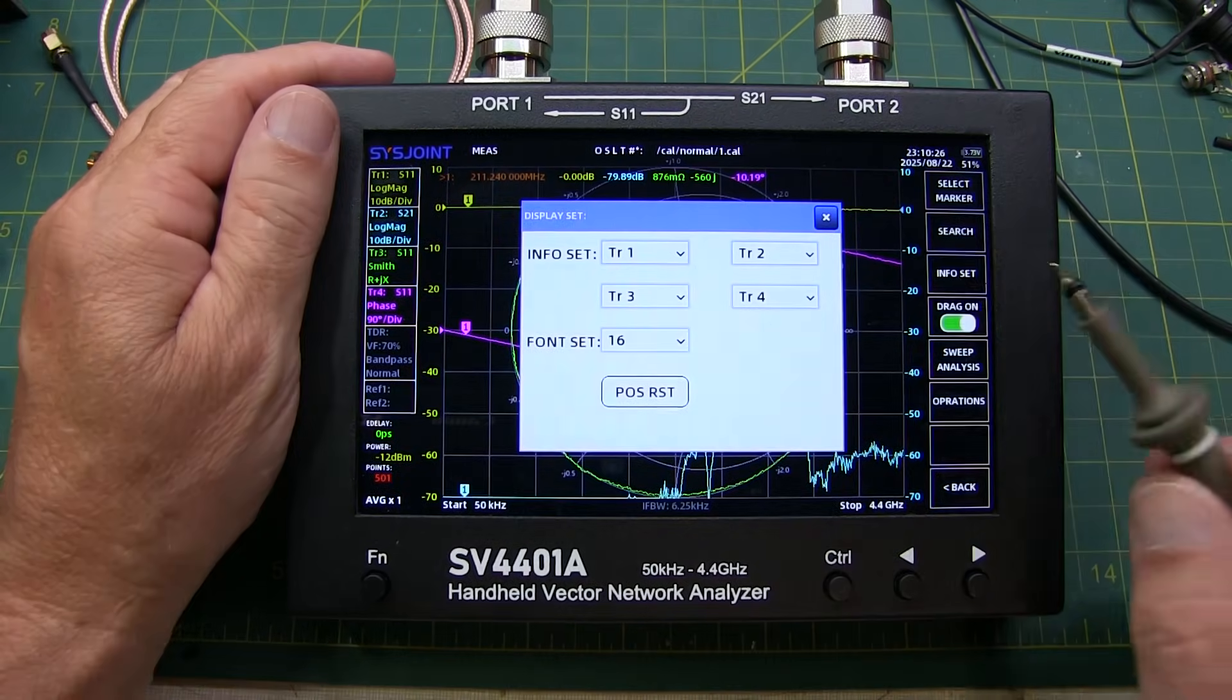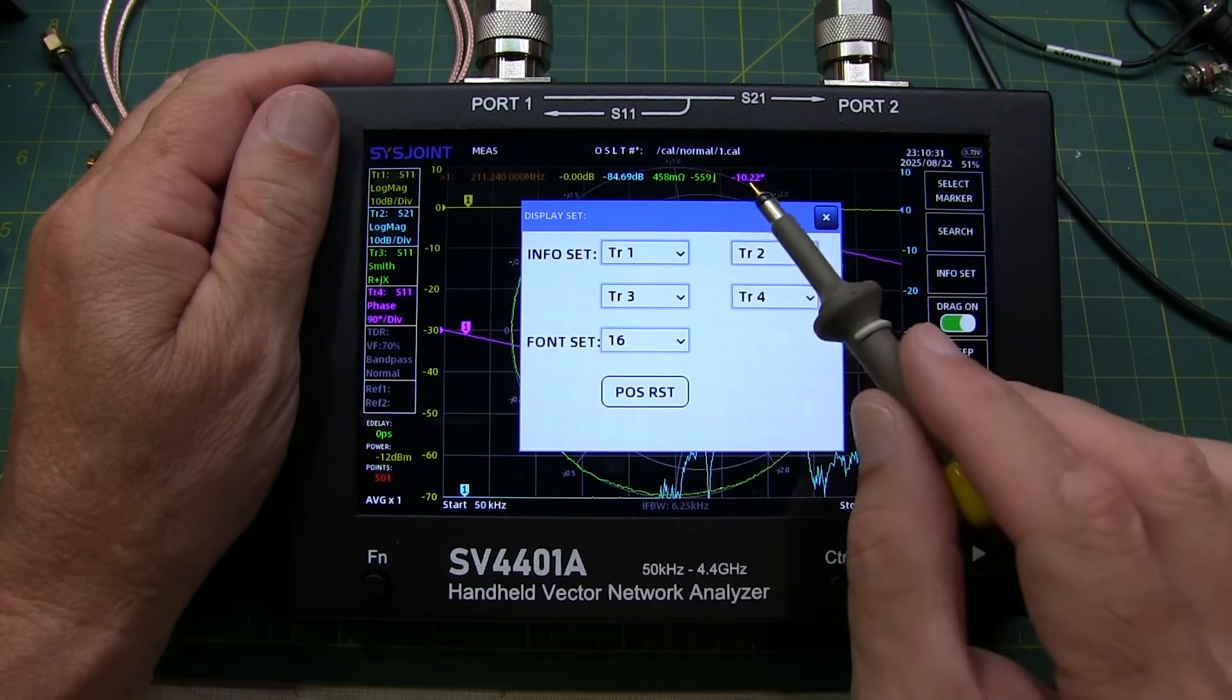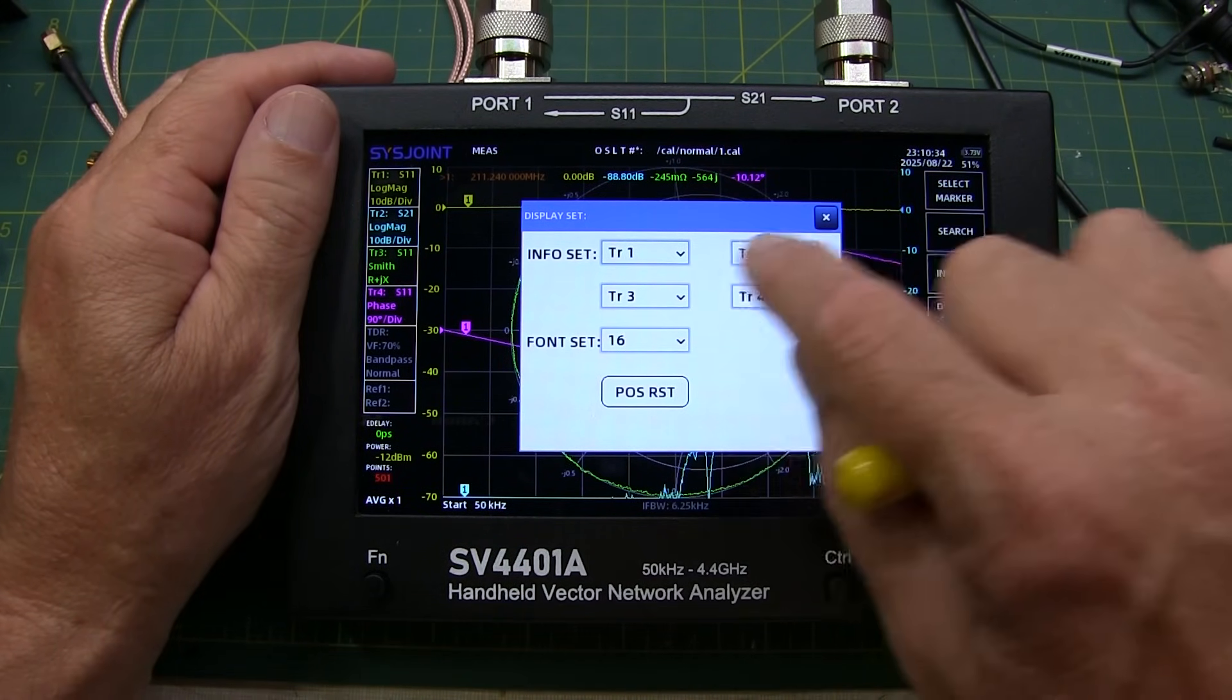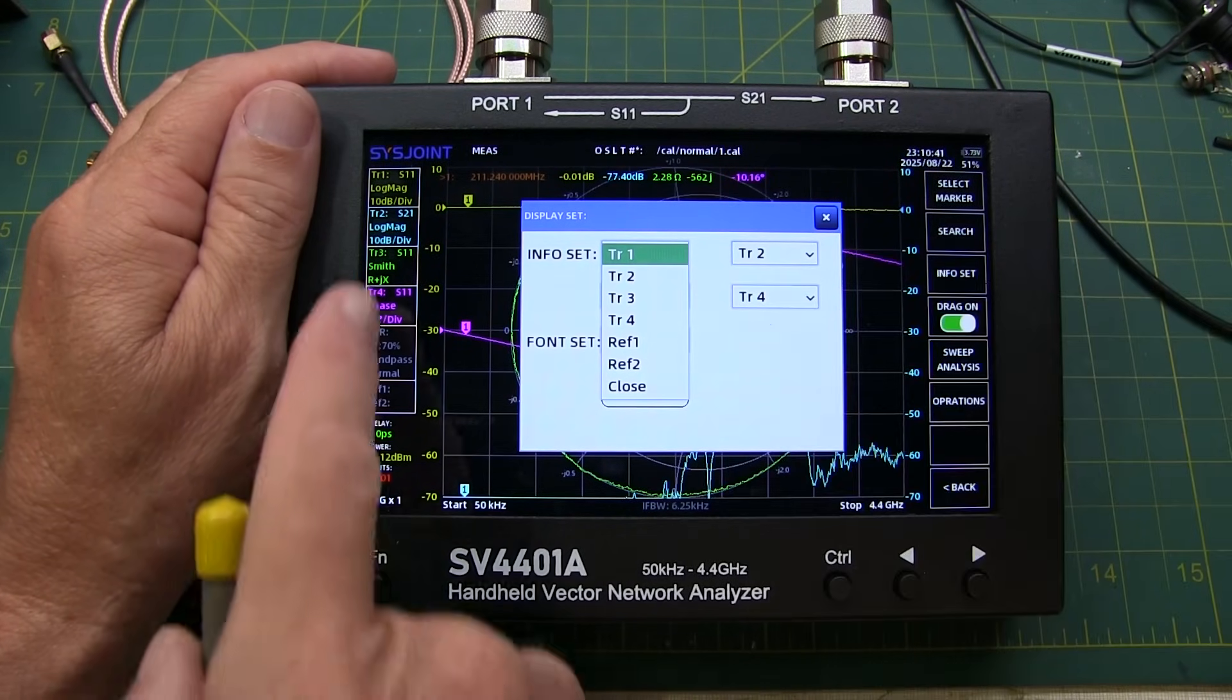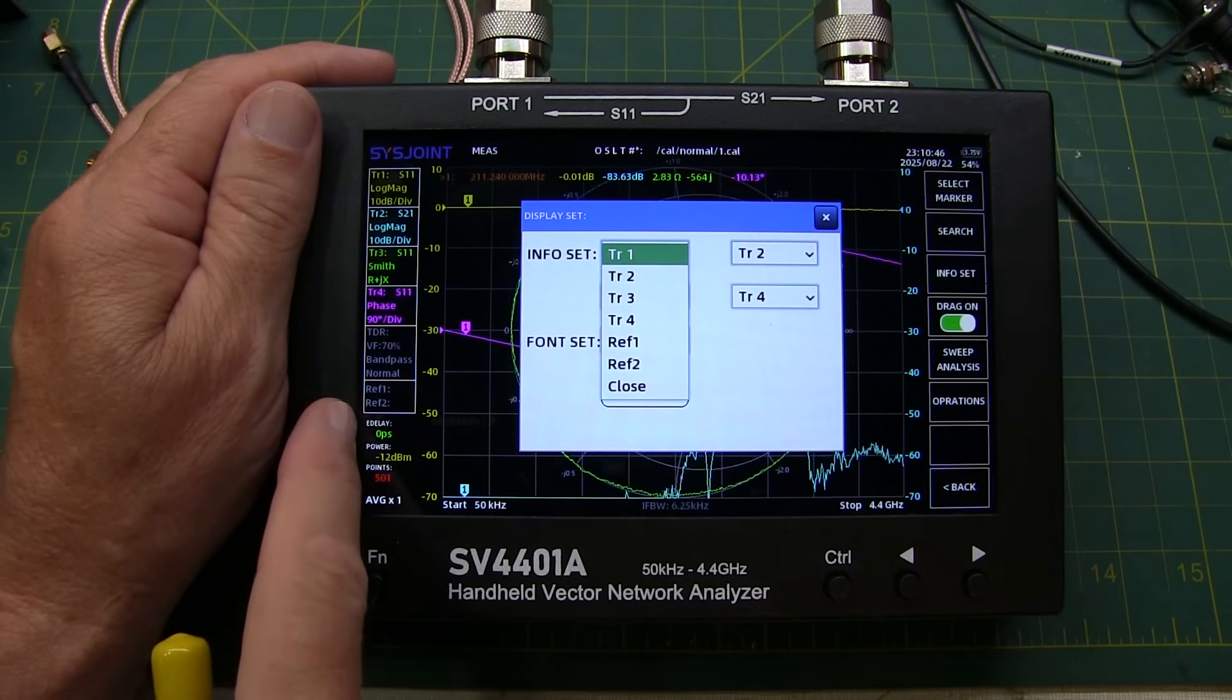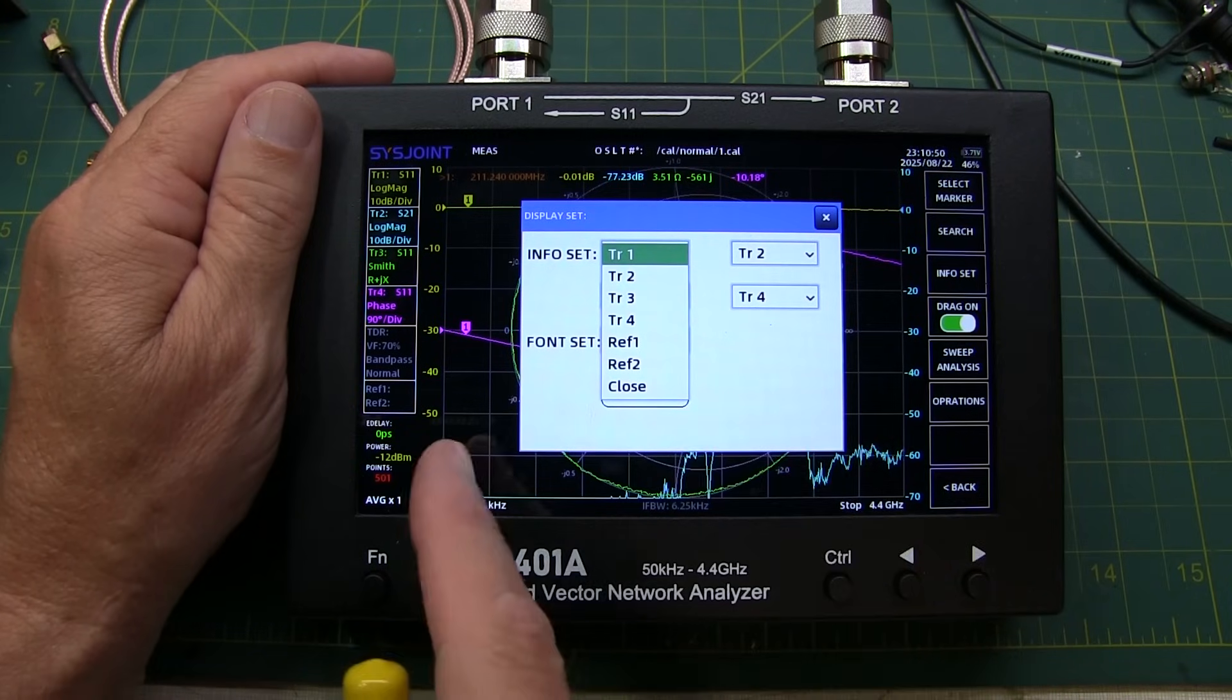The info set allows you to determine which marker readouts or what traces are going to be read out in the marker readouts. So I can pick from trace 1 through trace 4, which are these four traces here. You can also pick from reference traces as well. We can actually take any of these traces and bring up the two different reference traces up to make comparison measurements between one measurement and then another configuration.